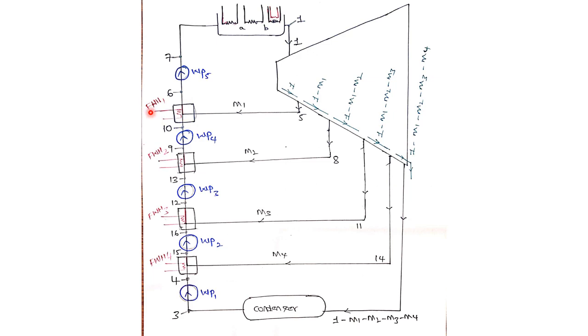No, definitely not. This particular heat which is added here comes from the exhaust of the turbine. So it is considered as the heat quantity which is already present in the system. You are not giving new heat to the system. That means you are not burning the fuel to heat up feed water heater 1, feed water heater 2, or any feed water heaters. You're just utilizing the heat which is available at the exhaust of the turbine to heat up this particular thing.